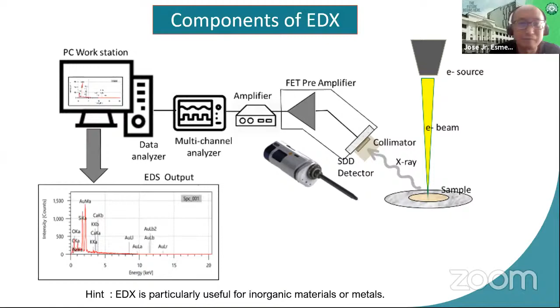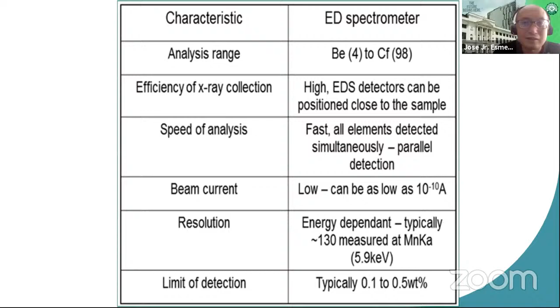So what are the advantages of EDS? It has a good analytical range. It has very efficient X-ray collection. And analysis is very fast. It can show you a lot of details at the same time. And then resolution is dependent on the energy. That means you need a higher acceleration voltage in order to produce more ionization, so that you get a lot of elements. Okay, but it is limited: it can only be used from beryllium, atomic number 4, or up. You cannot see hydrogen because it's not possible, because of the very light atomic number.